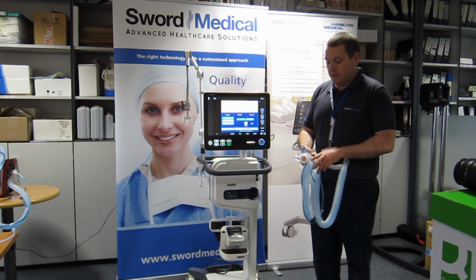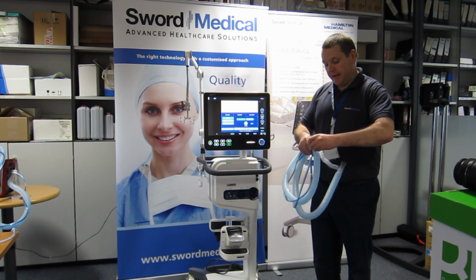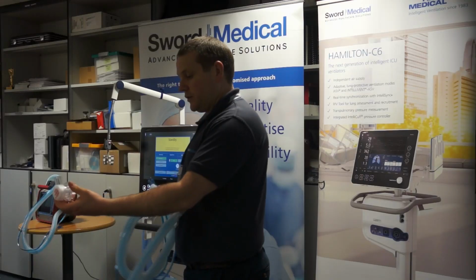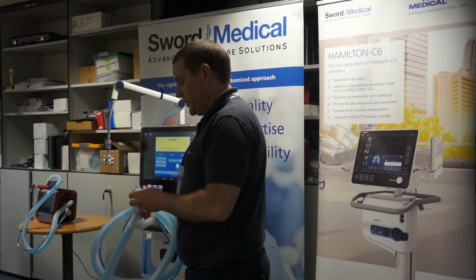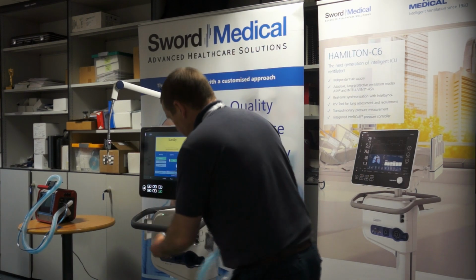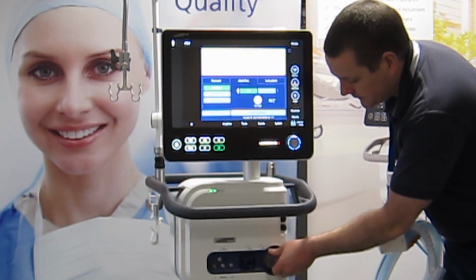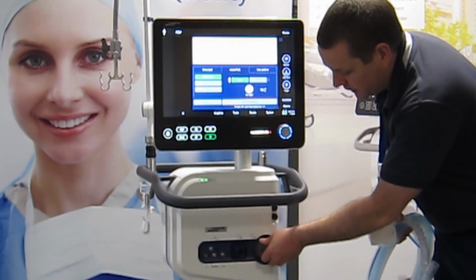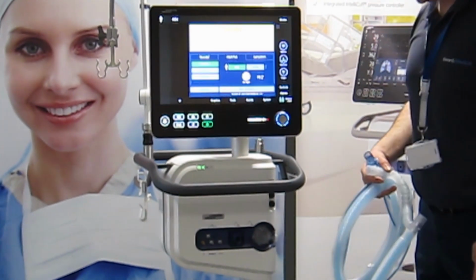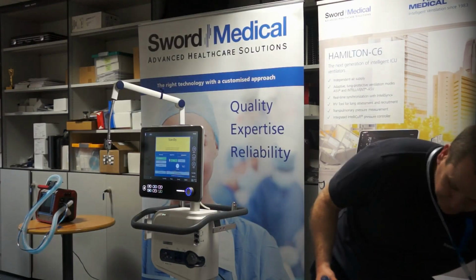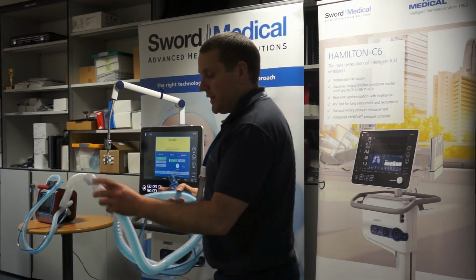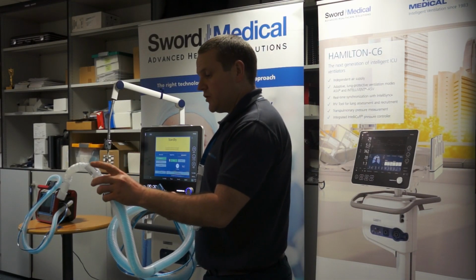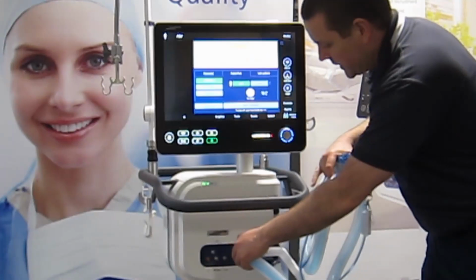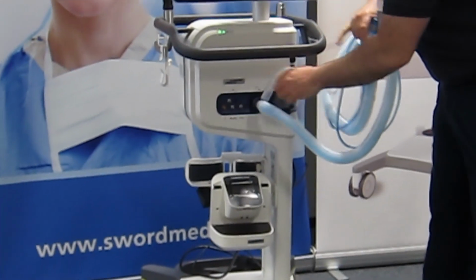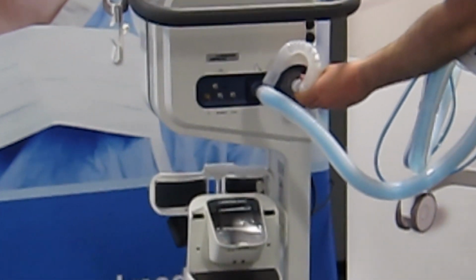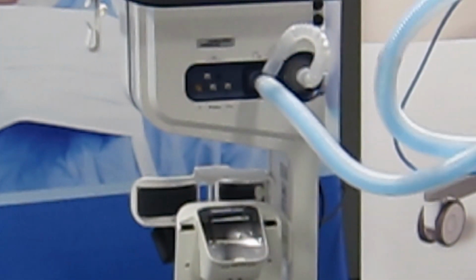Here, I'm going to take off my expiratory valve. You've got a dust cover on the expiratory valve that you take off before you put it on. And then the expiratory valve plugs onto the expiratory port here, all the way anti-clockwise to get it in fully, and then it gets a 1/10 turn clockwise to lock it in. And then I've got my inspiratory limb, just marked inspiratory, which plugs onto my inspiratory port here. And then my expiratory limb, which plugs onto the expiratory valve.